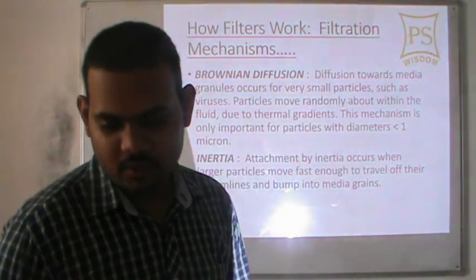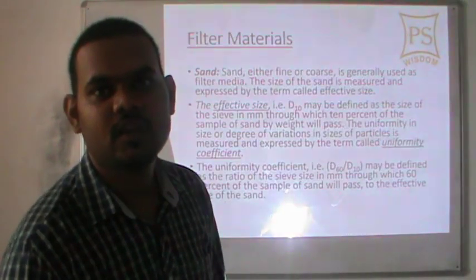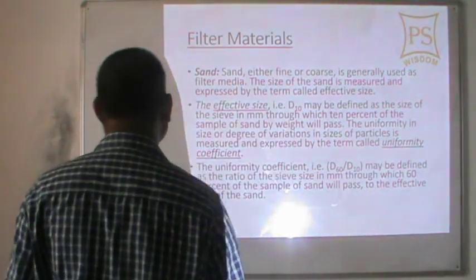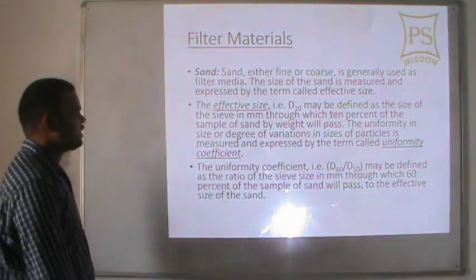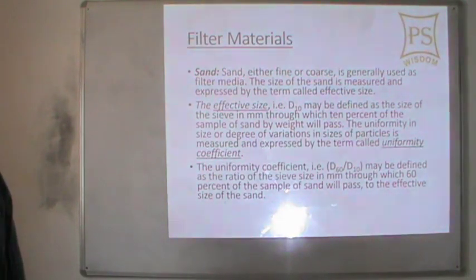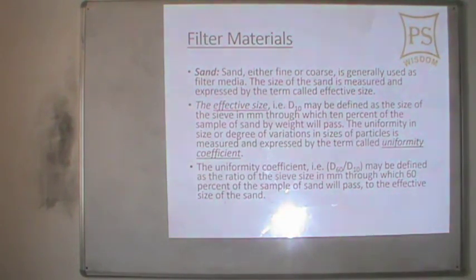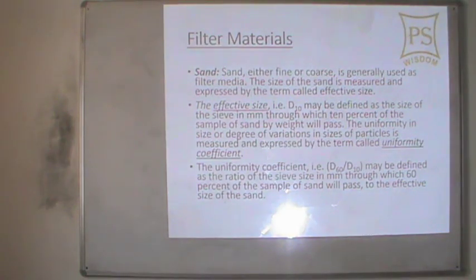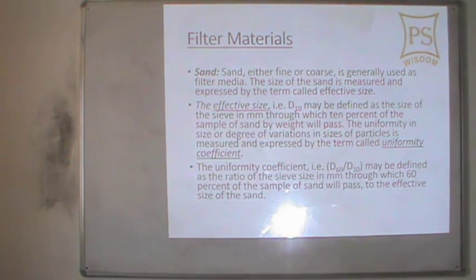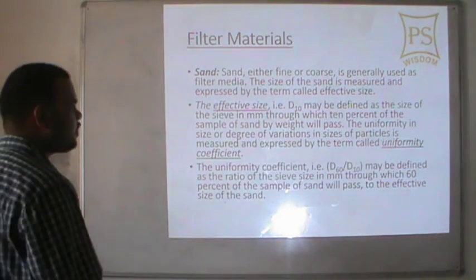Attachment by inertia occurs when larger particles move fast enough to travel off their streamlines and bump into the media grains. As for filter materials, sand — either fine or coarse — is generally used as the filter media. The size of sand is measured and expressed by the term called effective size, D10, which is defined as the sieve size in mm through which 10% of the sample sand by weight will pass.